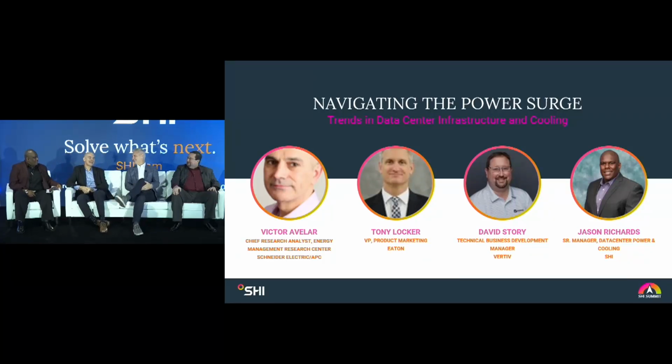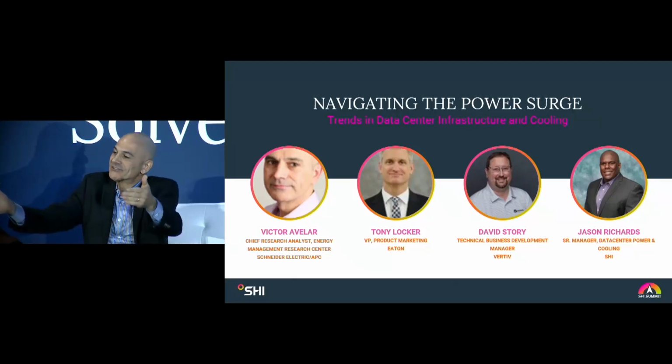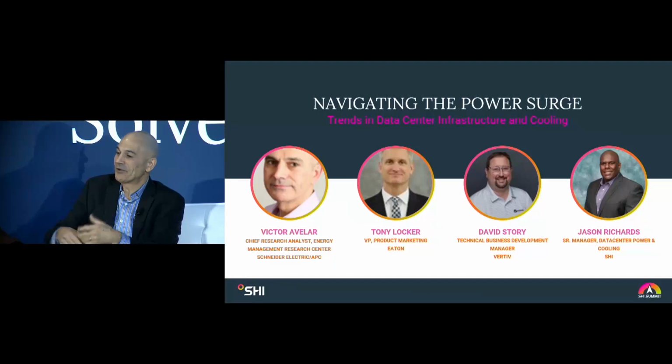Ask the audience. Well, I think it's just a matter of being comfortable with it. Right now, it's kind of fear of the unknown. We've had water in data centers for many years, decades in fact, with the chiller plants. It's just that they're in the back room somewhere, and only the pipes come into the data center. They were building big ditches in the subfloor for the event where the steel pipe just cracks and lets a bunch of water out and floods your data center. They stopped doing that. I don't see too many data centers building that way.